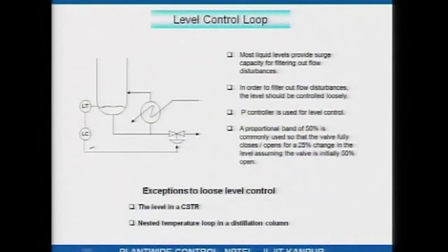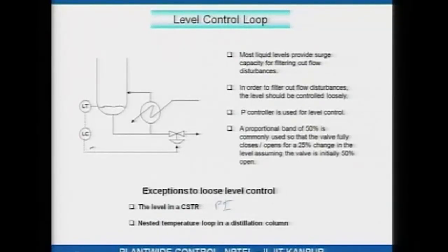Exceptions to loose level control exist. One example is level control in a CSTR: in a CSTR, the tank level affects residence time; more holdup means more residence time means more conversion, which affects downstream units and recycles. To hold conversion constant, level in a CSTR should be controlled tightly — offset is not acceptable — so level controllers in a CSTR may be PI type. Another exception is a nested temperature loop in a distillation column, which will be discussed when we cover distillation columns.